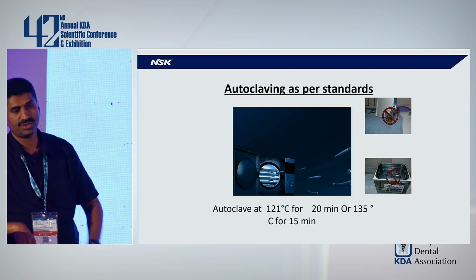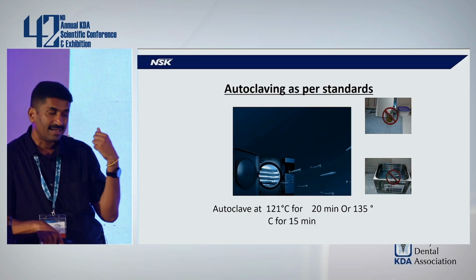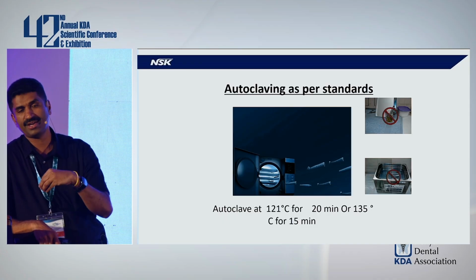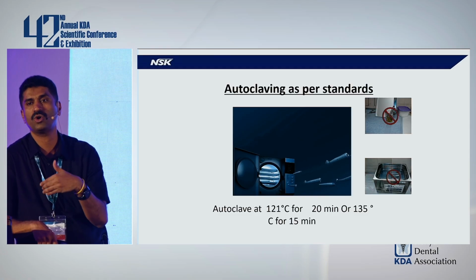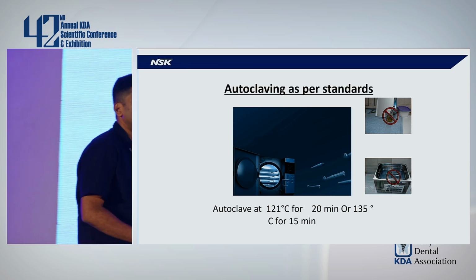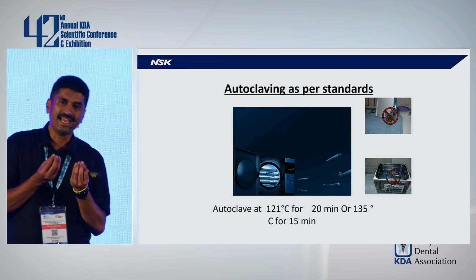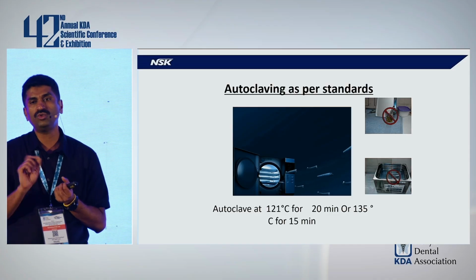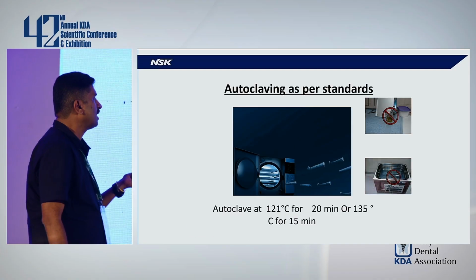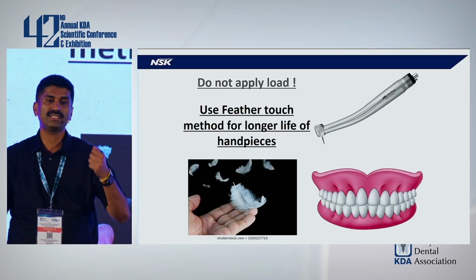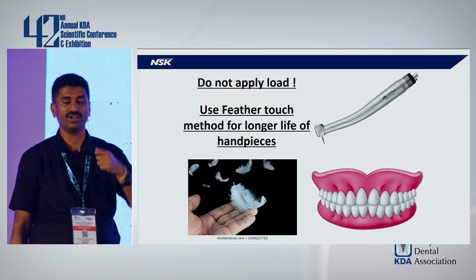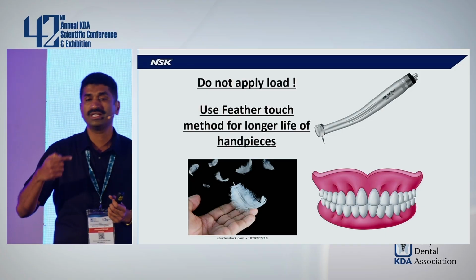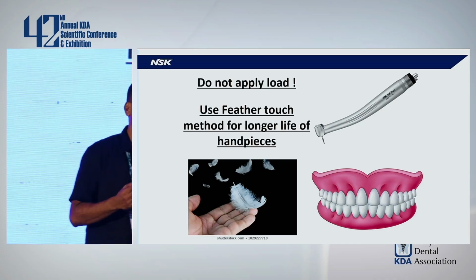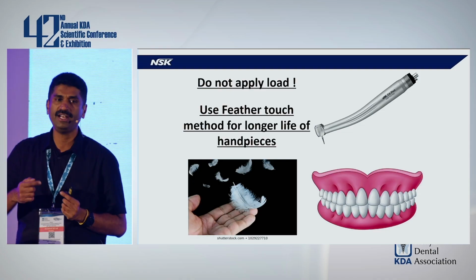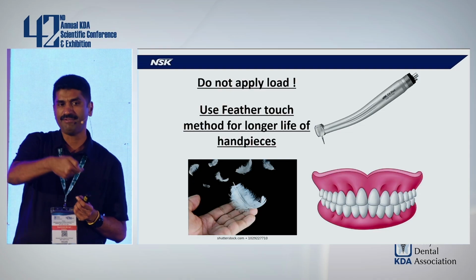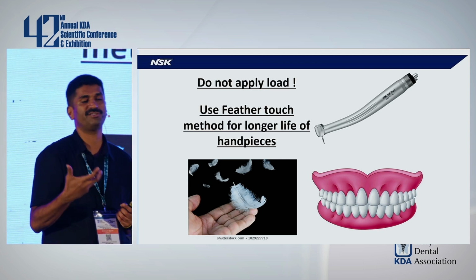Why we say you should not use chemical solutions: the chemicals you use will have a reverse reaction with the retainers of the ball bearings, which will cause early damage. Why do we not recommend an ultrasonic bath? Because the vibration of the water molecules will create movements of the ball bearings, resulting in wobbling of the handpieces. Okay. Last but not least, please use a feather touch method for cutting the tooth. The burs you use run at a very high speed of 400,000 revolutions per minute. At such speed, if you apply load on the patient's tooth, there will be a reverse effect on the ball bearings and early damage of the handpieces will take place.